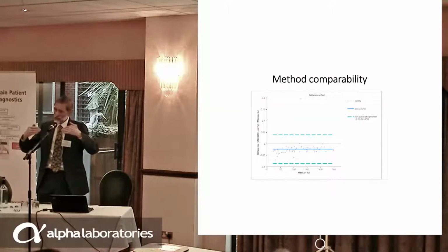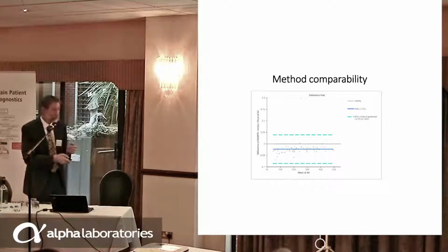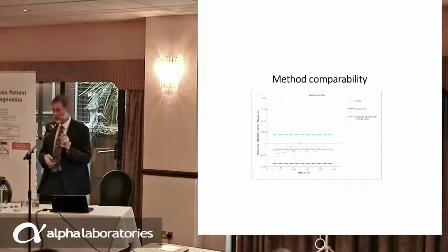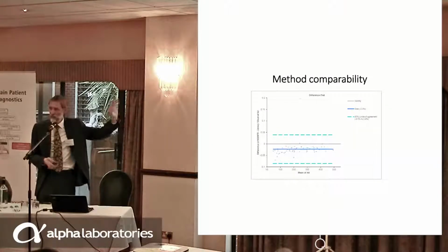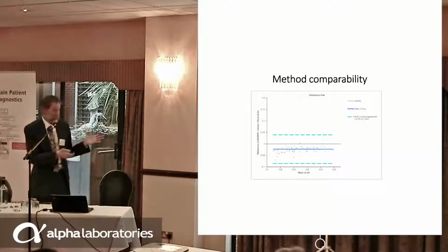So actually taking it over a number of days or weeks so that you get a true estimate of the true relationship between the two methods is important. And of course, one of the things to comment on is over a period of time, methods can drift by 2%, can't they? The same method on the same analyzer, new calibration lot numbers, sometimes you see these sorts of differences on a regular basis, I would say. So contextualizing that is important.